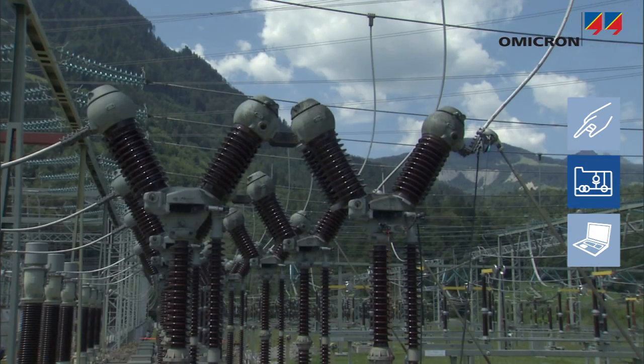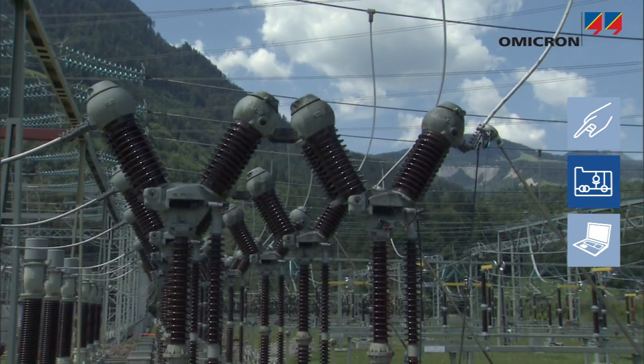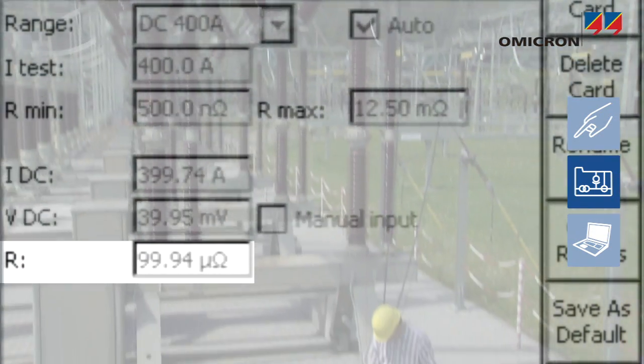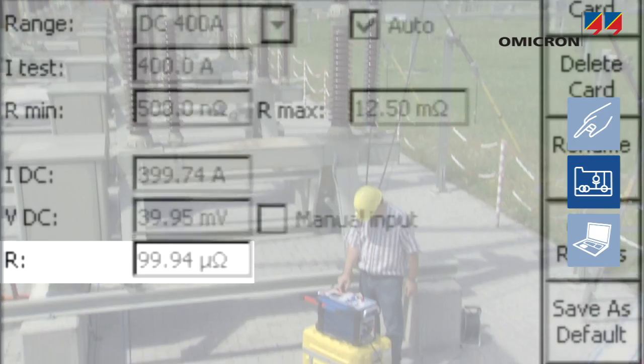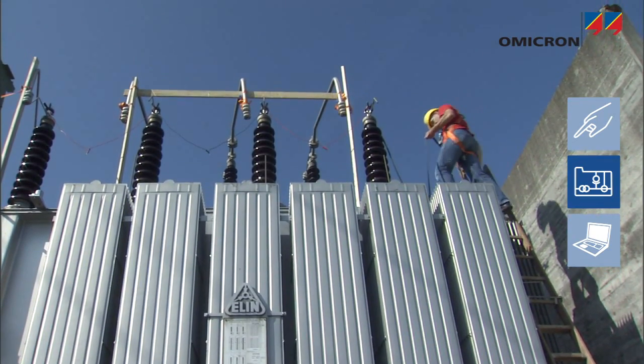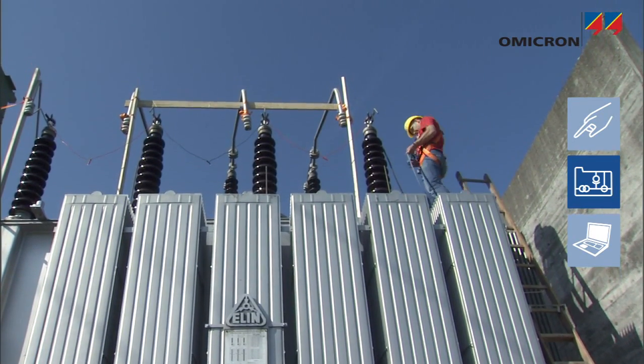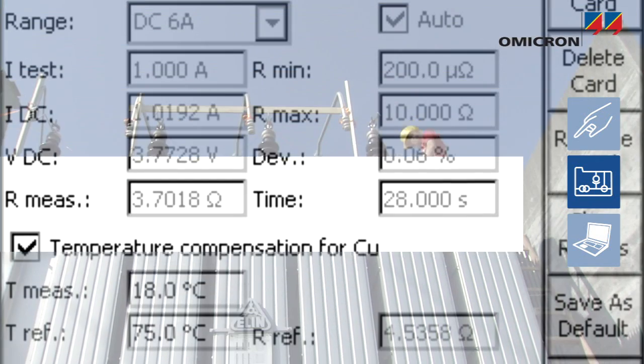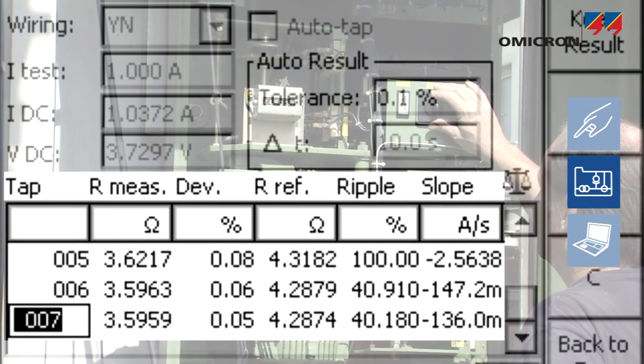The contact resistance of circuit breakers can also be measured. For power transformers, test cards aid the user in measuring the ratio, winding resistance, and tap changer, as well as the power factor and capacitance.